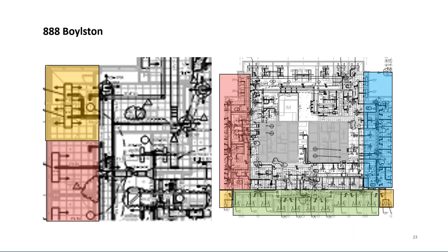And even in that case, you can see the blow up on the left, the orange box. We had like 10 feet of chilled beam in a corner office, and that was on the west facade. That's a lot of chilled beam for a small office space. So it was important for us to make sure that this was going to work. It did work. We did the right level of analysis, but you do have to be careful with that.